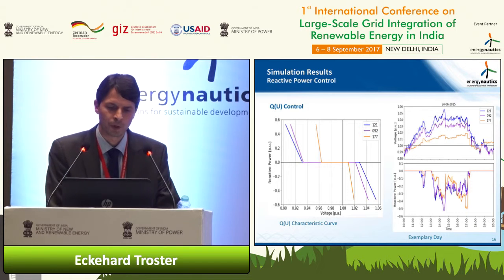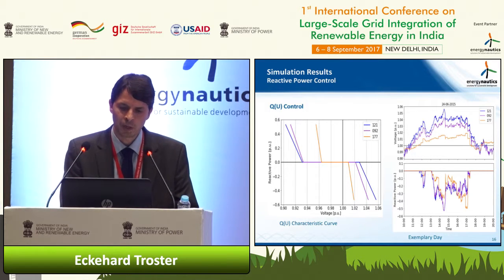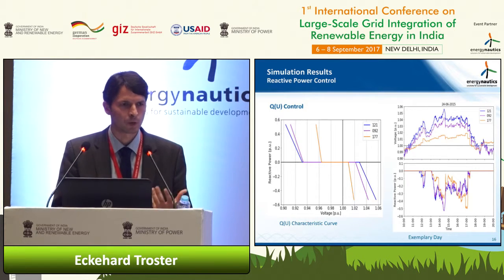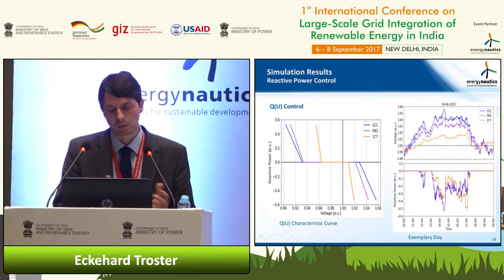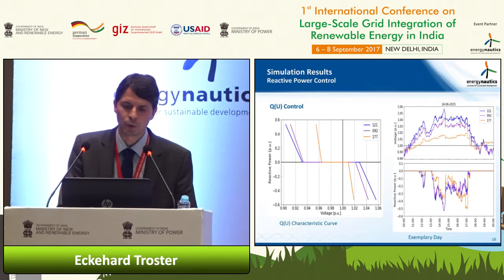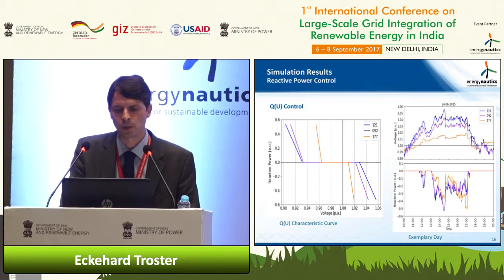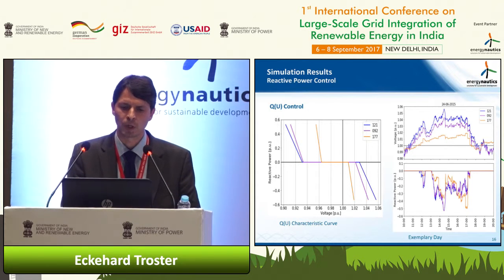Typically, you have a certain dead band where you don't want to do anything, because reactive power normally introduces additional loading and losses. Therefore, you don't want to do it. You just want to use it when you really need it.